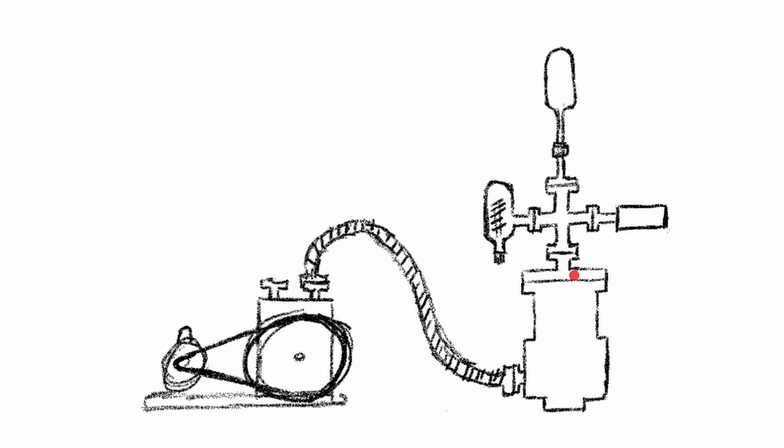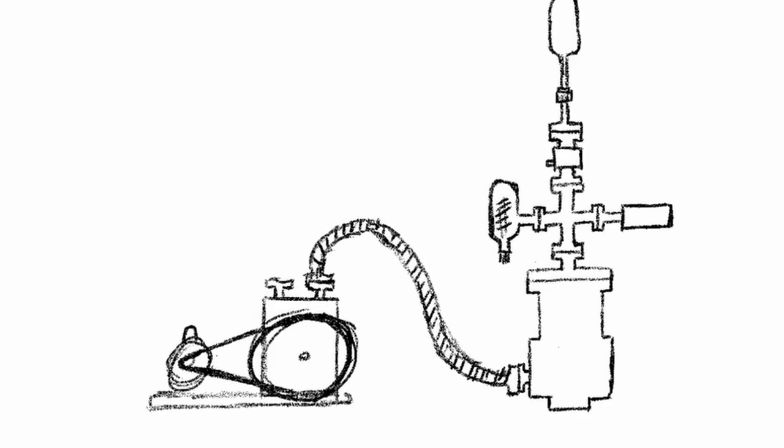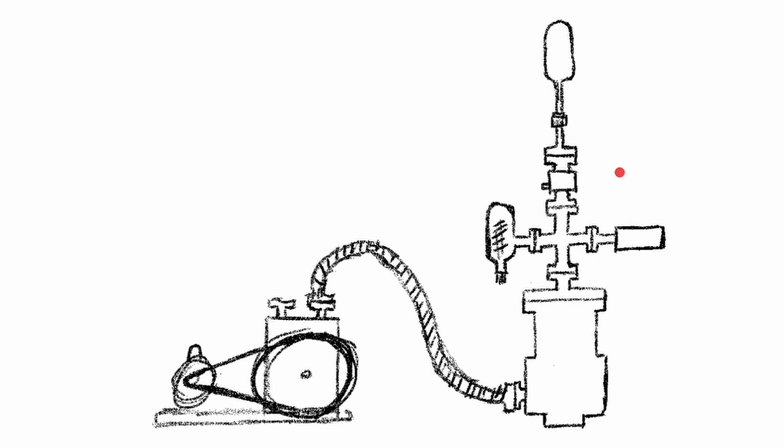Okay, so now we can create a vacuum and we can measure a vacuum, but what happens if I find a leak and I need to take the tube off the system to fix it? Remember, we can't expose the running turbo pump or the hot ion gauge to atmospheric pressure. Well, what we could do is turn off the ion gauge, then turn off the turbo pump, let the turbo pump spin all the way down, and then turn off our roughing pump and remove the tube from the top of the system. But it would be a lot easier if we just had a valve that we could shut off to separate the tube from the rest of the vacuum system. This does improve the situation, but actually not by a whole lot. Because once we close this valve and remove the tube, if we put the tube back on, the tube is now back at ambient pressure. And when we open this valve again, we'll be exposing both the ion gauge and the turbo pump to the atmosphere inside of the tube.